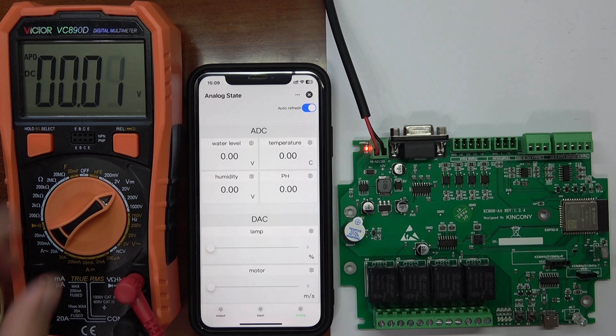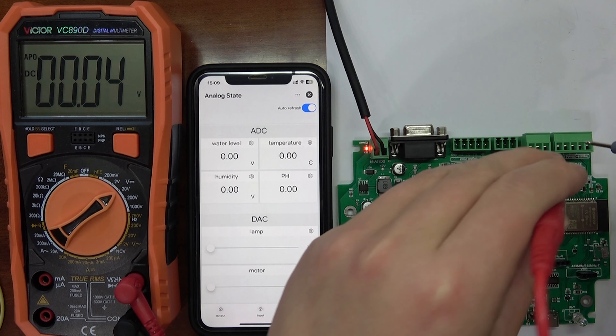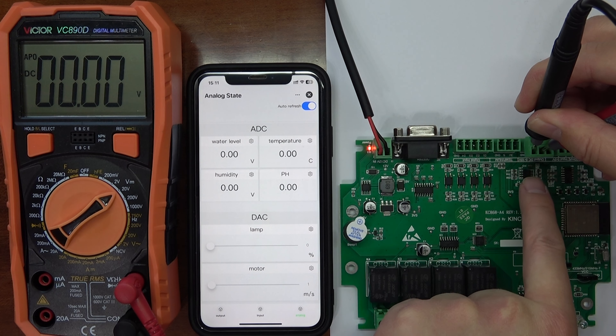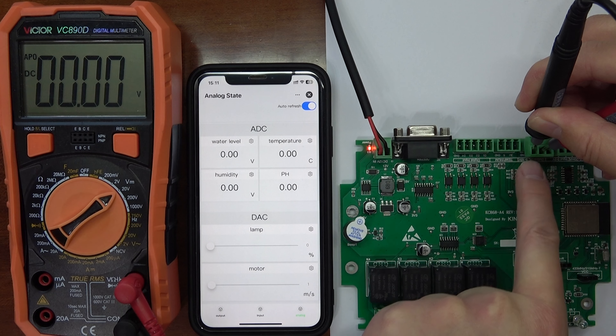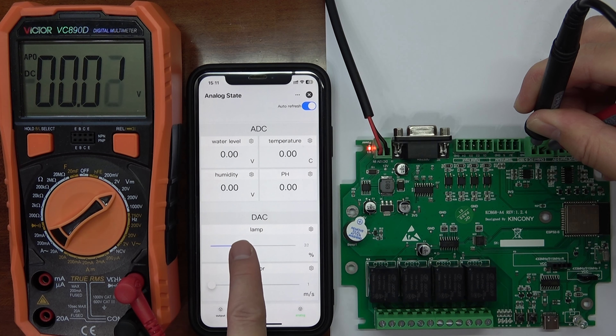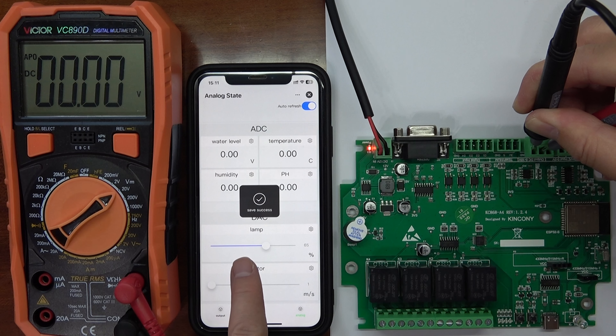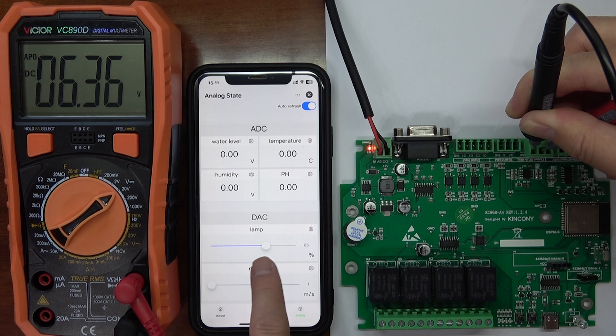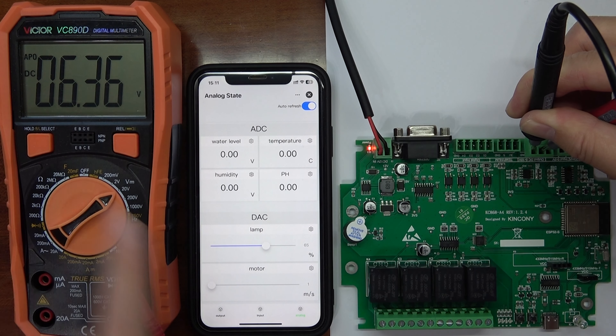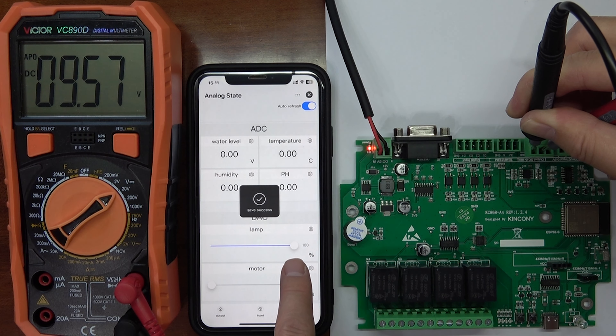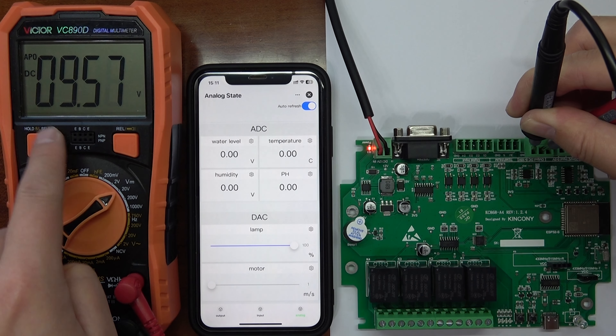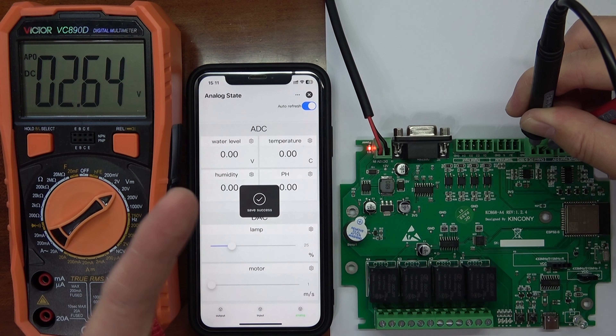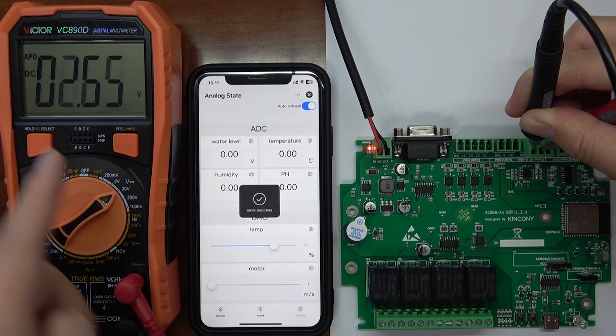You can see I can use this multimeter to test it. I have tested this digital analog output channel 1. I can change this scroll bar and you can see the voltage changes. This is 65 percent — that is the voltage. If I change to 100 percent, it is almost 10 volts. So according to your input, you can change to different voltage outputs.